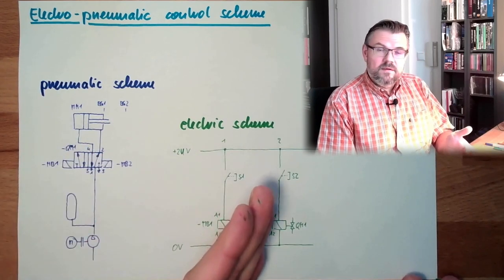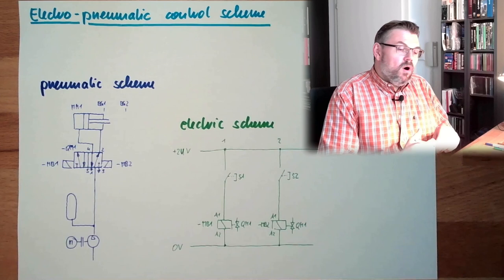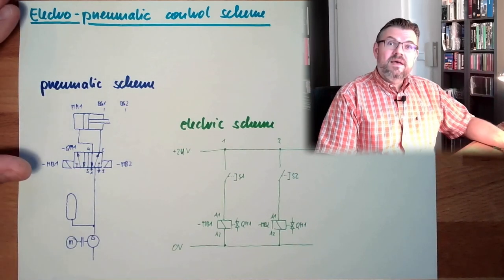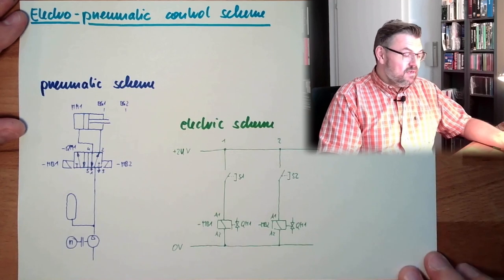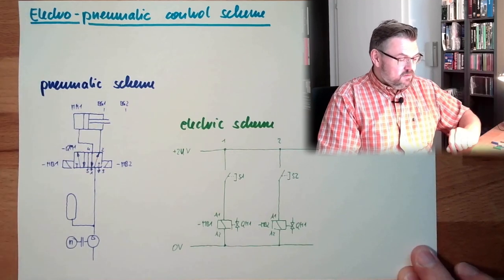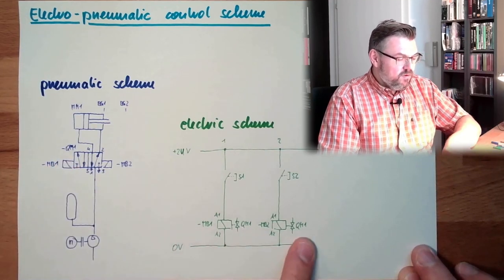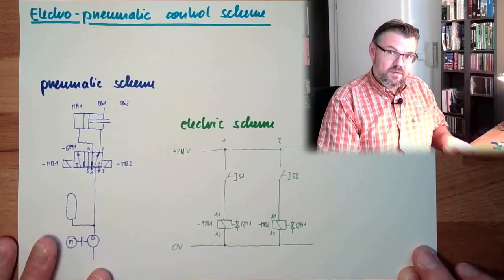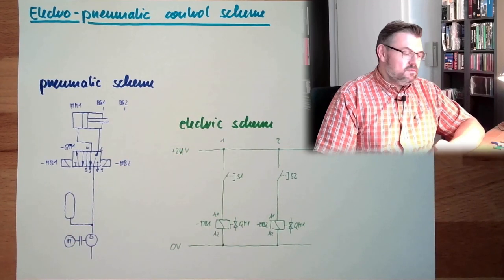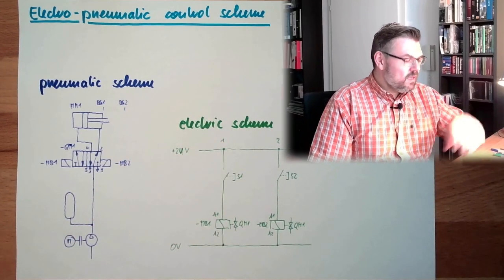So we have two parts, pneumatic scheme, electric scheme. Might be in one diagram, one sheet, or might be in separate sheets. The bonding elements are the names. You see, there is QM1, I find QM1 here and here, there is MB1 and so on. I can map these things, and then I realize what is happening.